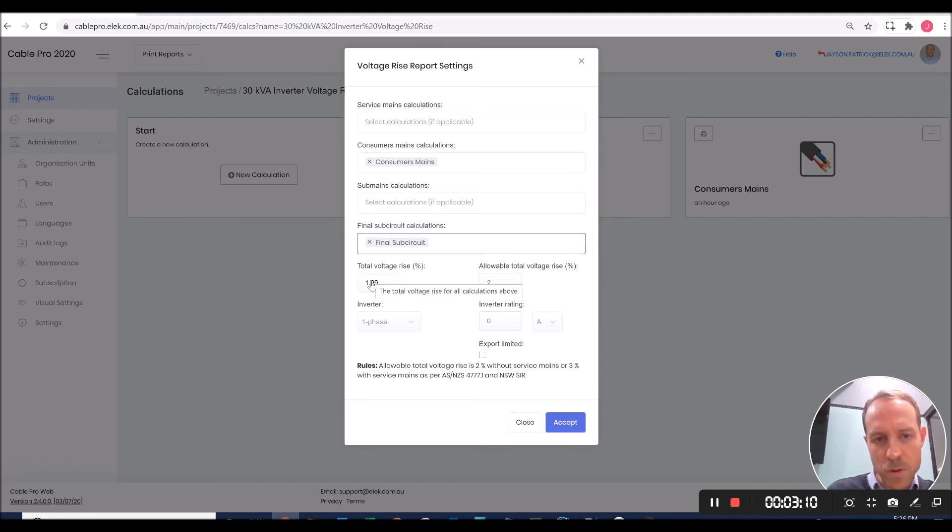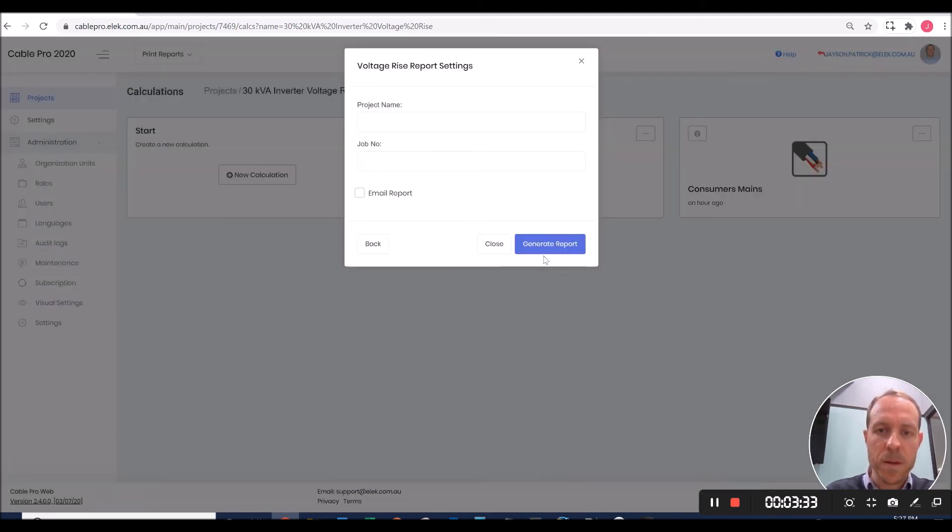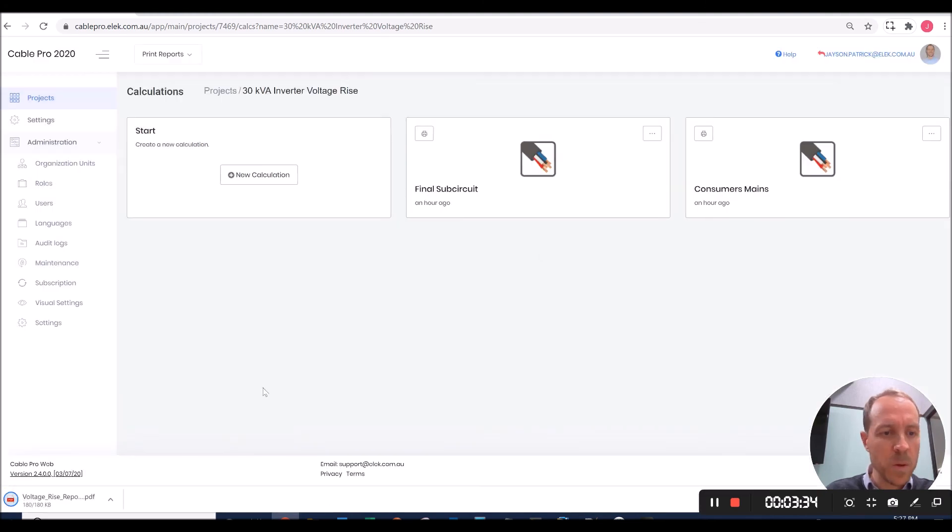The total voltage rise is calculated to be 1.99%. Our allowable voltage rise is 2%. Our inverter is a three phase. The inverter rating is 30, in this case kilowatts or kVA. I'll accept that. I'll generate the report.